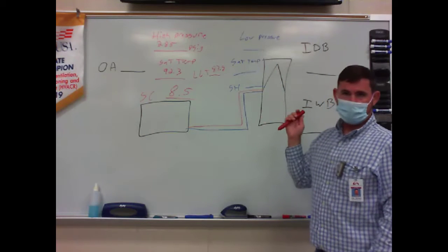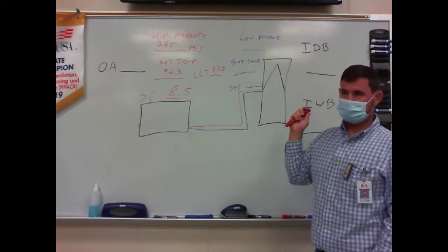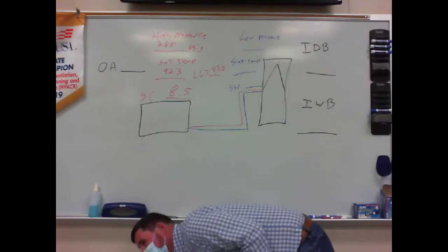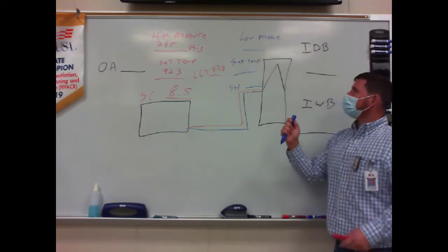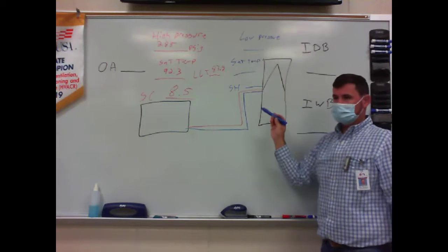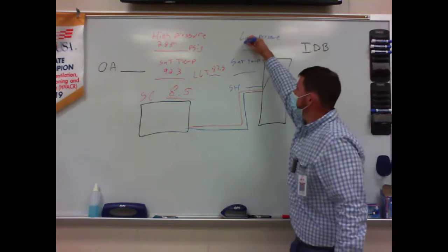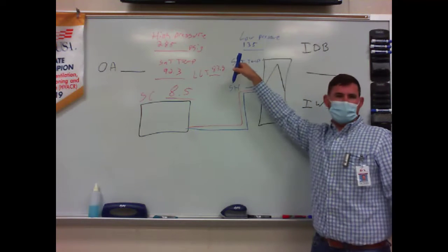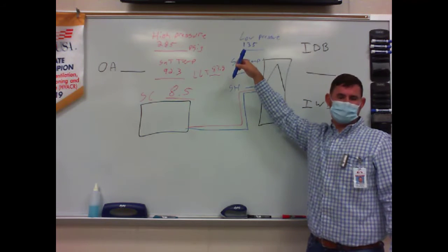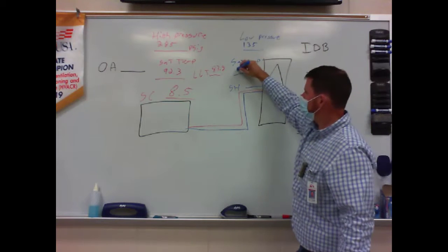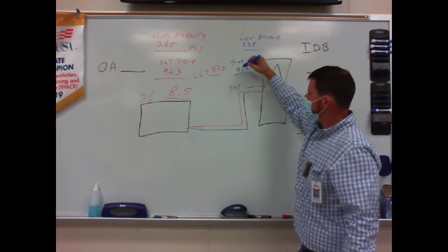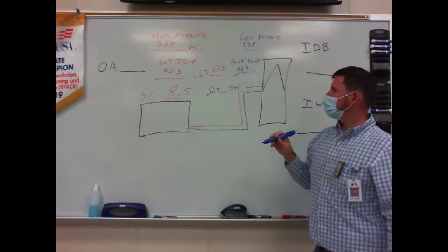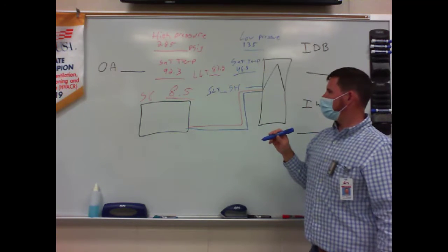What would y'all get on your low side pressure? 135. Which means I'm saturating at what temperature? 46.8 degrees. And what was your suction line temp? 47.